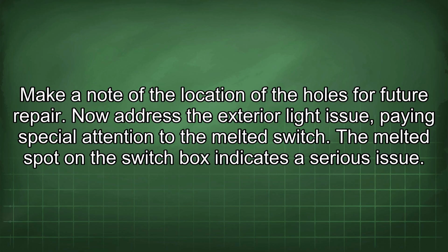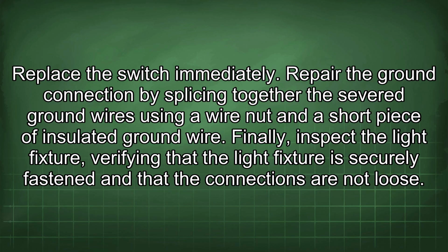Now address the exterior light issue, paying special attention to the melted switch. The melted spot on the switch box indicates a serious issue. Replace the switch immediately. Repair the ground connection by splicing together the severed ground wires using a wire nut and a short piece of insulated ground wire. Finally, inspect the light fixture, verifying that the light fixture is securely fastened and that the connections are not loose.